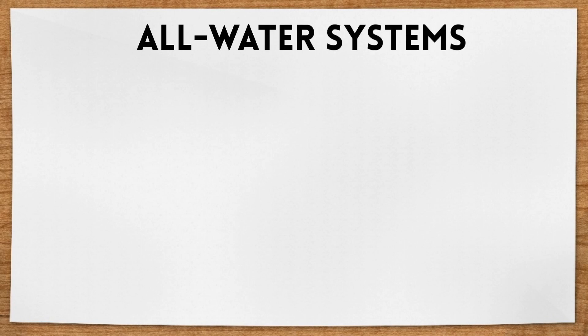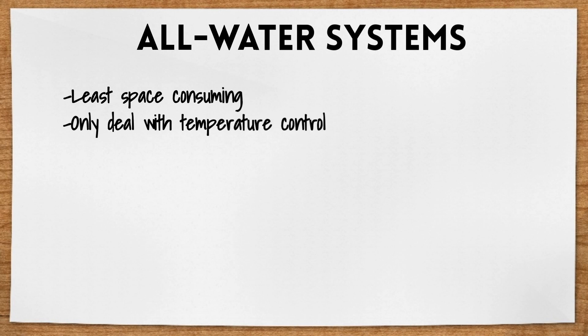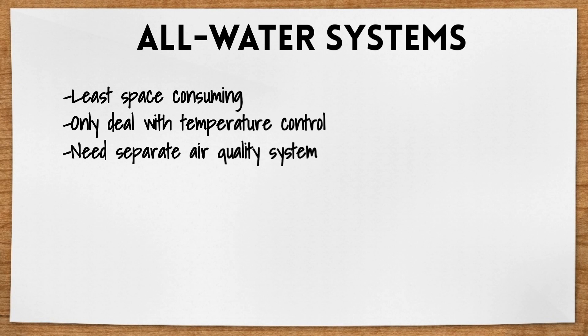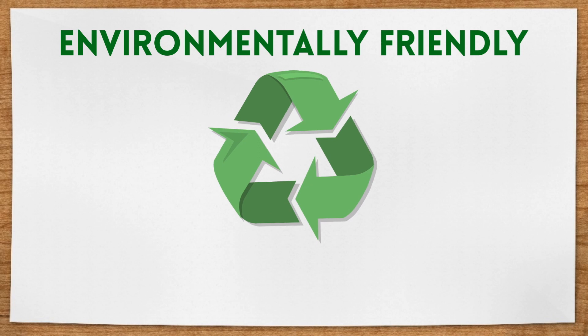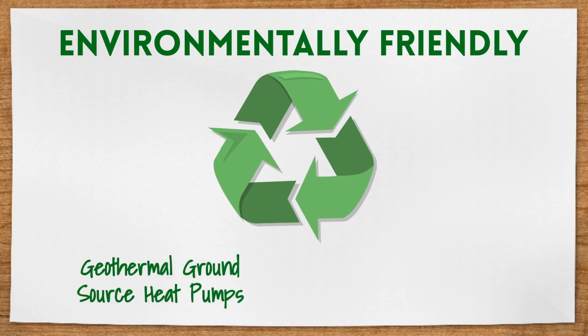The third category is all water systems. These are the least space consuming systems since their distribution trees are made entirely of thinner piping. However, they typically can only deal with temperature control, and air quality must be dealt with using a different system. The most common example of all water systems is the fan coil unit. There are also some environmentally friendly systems to know, such as geothermal ground source heat pumps and the concept of the economizer cycle.